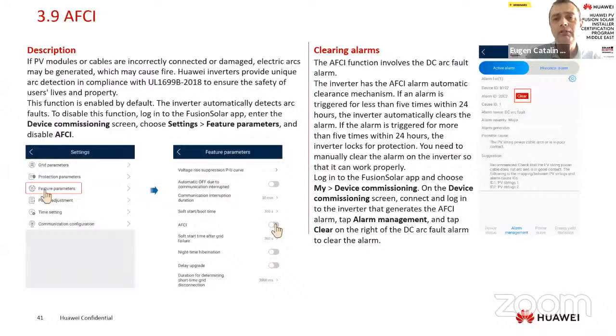Normally, in general, if the inverter generates an alarm, we have a fault, of course, and it will stop to protect first. After that, if you fix the alarm, normally the inverter will clear the alarm automatically and start to produce. In this situation, if the alarm is generated more than 5 times in 24 hours, you need to clear the alarm manually. How? First, connect locally to the inverter, and from the alarm management, select the alarm and clear it. Of course, first you need to fix the problem. This alarm clear will not solve the problem, yes? And second, we have the option in the web portal, clear the AFCI fault alarm. This is the second option.